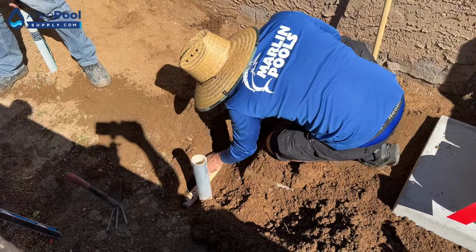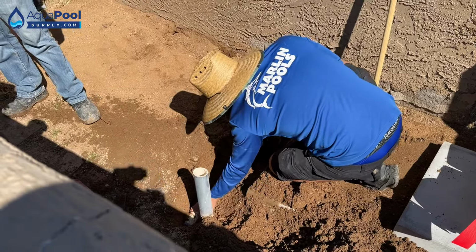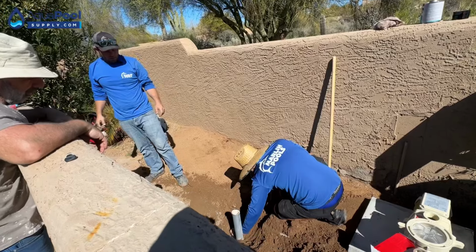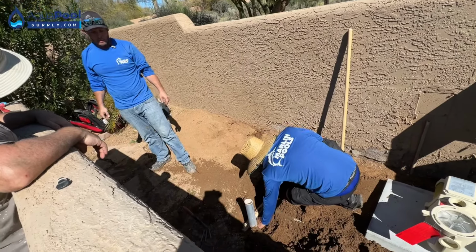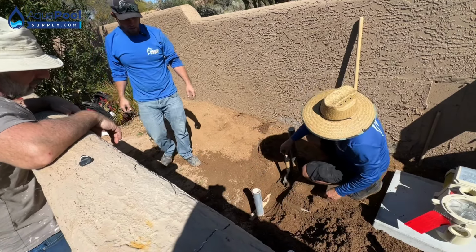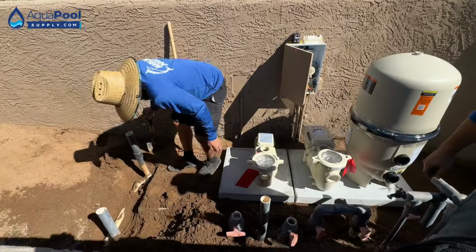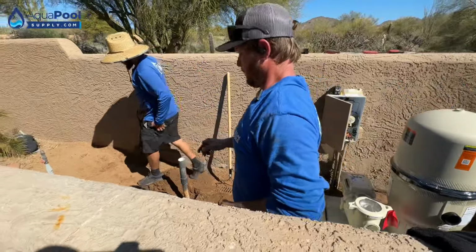Yeah. I'm pretty good at pulling on it too. I can tell when it has that breaking point. Yep. It gets brittle after a while, even underground. It can. Yeah, and you never know if it was really running in Schedule 40 underground. Oh yeah, I gotcha. I've run into some stuff that looks like Schedule 10. You barely move it, it just crumbles.